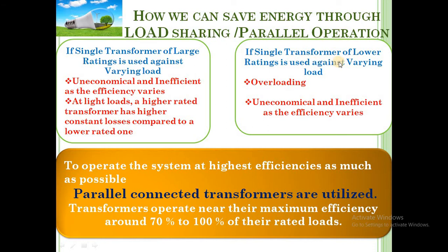Second case is, if a single transformer of lower rating is used, then suppose we have taken a 100 kVA transformer and we are loading it with 125 kVA. 100 kVA चा ट्रान्सफॉर्मर आहे आणि त्याच्यावर आपण 125 kVA चा लोड देतोय. So 25 kVA हे एक्स्ट्रा होणार आहे, and because of that there will be overloading, and because of overloading the transformer overheating problems and insulation failure problems will increase, and obviously it will be uneconomical and inefficient as the efficiency varies according to the load. So if a single transformer of large or lower capacity is used against varying load, then there will be uneconomical operation and reduced efficiency.